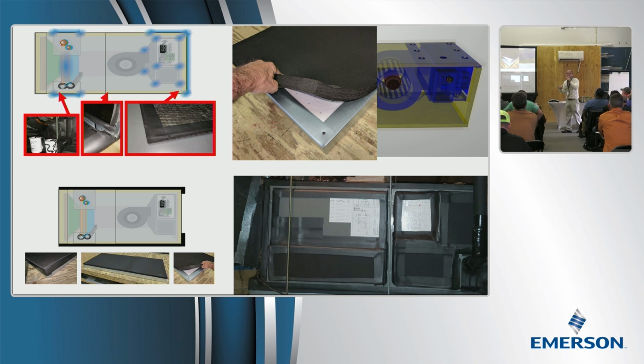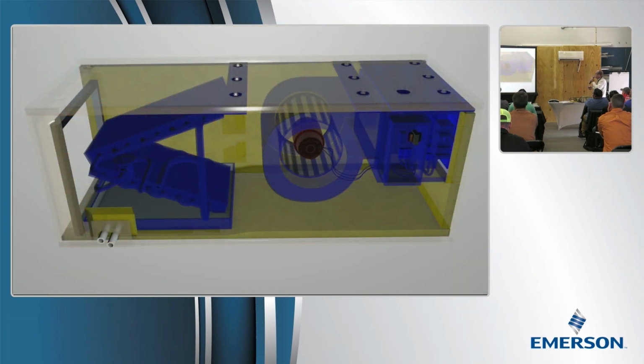In our climate, we have to come up with ways to deal with this, because we can't just let it drip all over the ceilings. So sometimes it's not particularly pretty. You can't hardly see this, but this is an air handler on trapeze hangers. That's one of the things you want to do, get it up high, don't let it be near a cold ceiling. It's got foam all over it because foam just doesn't want to sweat, kind of like the anti-sweat thing.